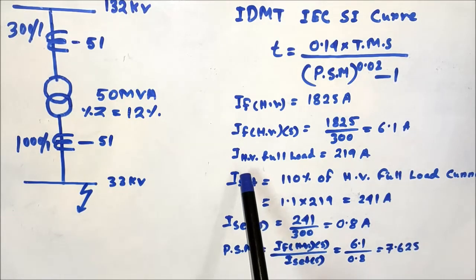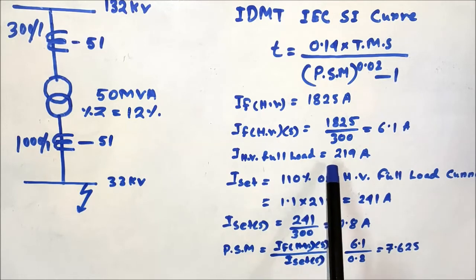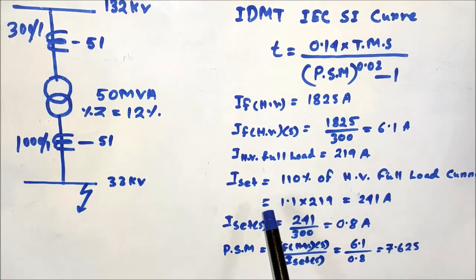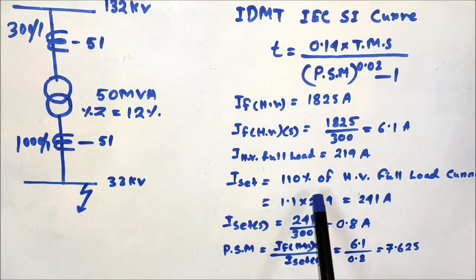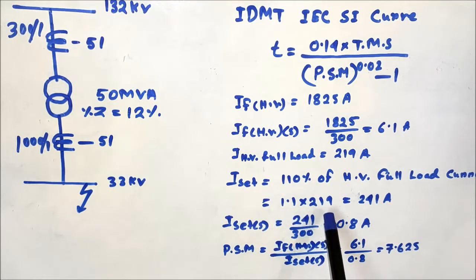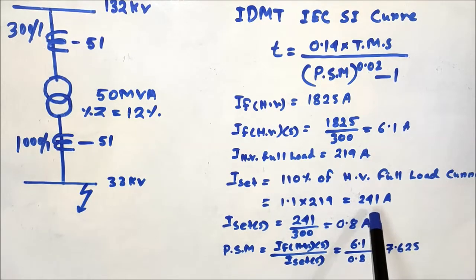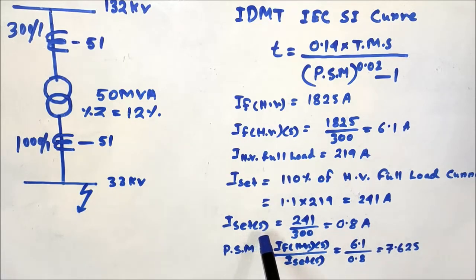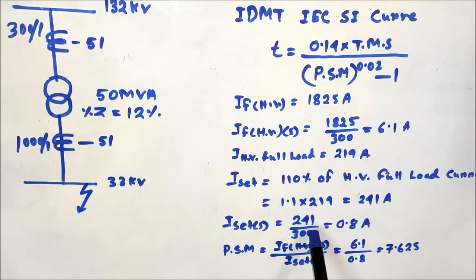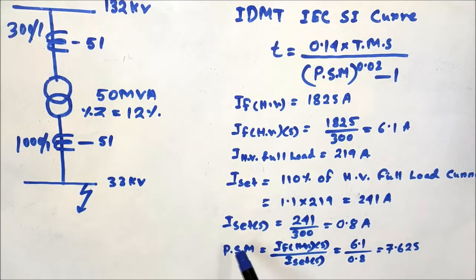The full load current on the HV side is 219 amperes. The current set value is 110% of the HV full load current: 1.1 × 219 = 241 amperes. Reflecting this to the relay secondary by dividing by the CT ratio of 300/1, the I_set secondary is 241 divided by 300, which equals 0.8 amperes. This is the setting for the HV overcurrent relay.